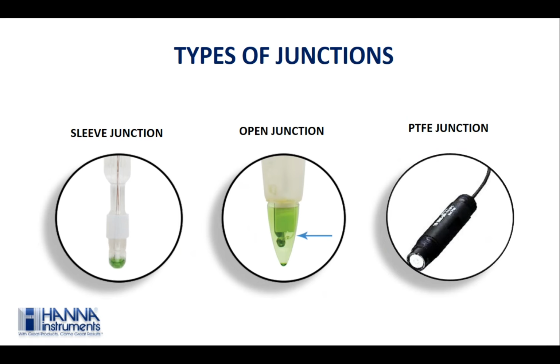Other types of junctions we have are sleeve junction, open junction and PTFE junction. The sleeve junction and open junction electrodes are used where clogging of the junction is most likely. In an open junction electrode, the reference electrolyte is in direct contact with the sample, thus giving high flow rate and fast response. And the sleeve junction electrode is used in samples that have high solid content and can easily remove the clog of the junction.